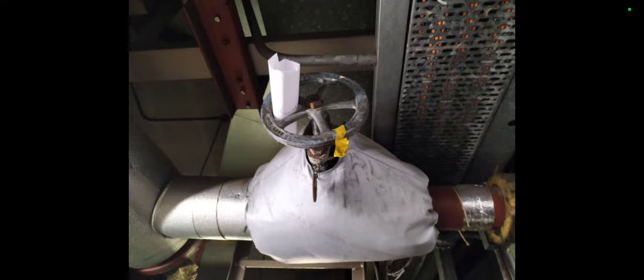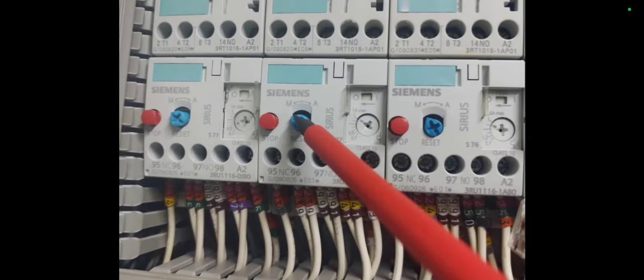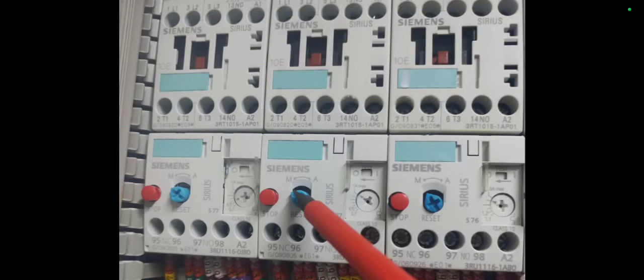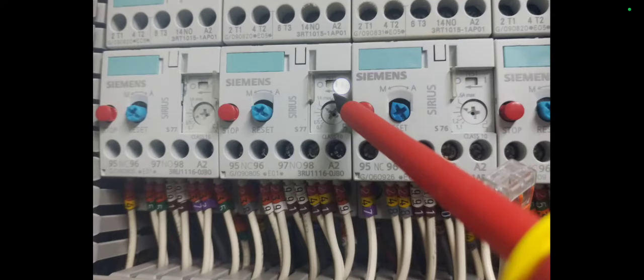And then if you leave a little note, at least they're aware. On a particular unit, I found the pump said overheated, and sometimes on these, if you're aware, they can trip the overcurrent. So you see, you have your setting of how many amps the overcurrent is set to, and if the pump draws more than 1 amp, for instance, in this scenario, it will trip. And then you have to look, and if you see this over here in the wrong place, at the moment it's in the right place, but if you see it in the wrong place, then you know that you need to turn the power off and then hit your reset.